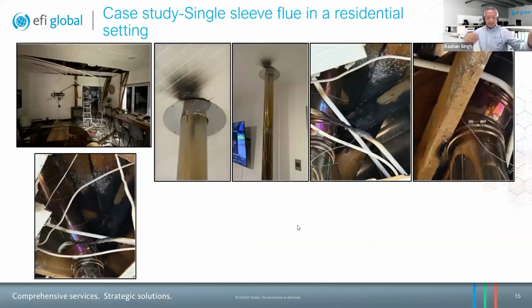But before I pass over to Werner, just a quick note. There is a misconception in the industry that this insulation material is adequate or effective. Normally it is rock wool or a ceramic insulation material that is designed to withstand heat for a particular life cycle or span. It's not designed to have heat imposed on it over a long period of time. They will fail, they will degrade, and you will have hot gases and heat being transferred through your flue pipes. Cool. And Werner, I shall pass over to you.